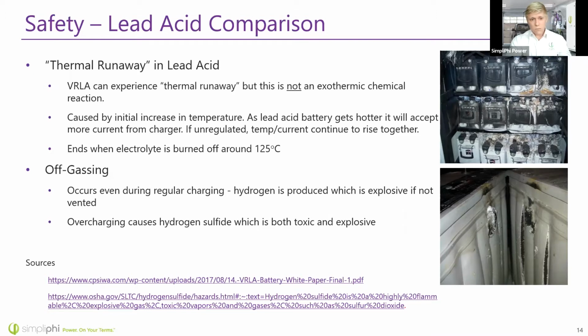Hydrogen is produced even during regular charging of a lead acid battery, but during overcharging, hydrogen sulfide is produced. Both hydrogen and hydrogen sulfide are explosive if not vented. As you can see here, these two setups were not vented properly, and it actually caused an explosion within the battery room because of a buildup of hydrogen.